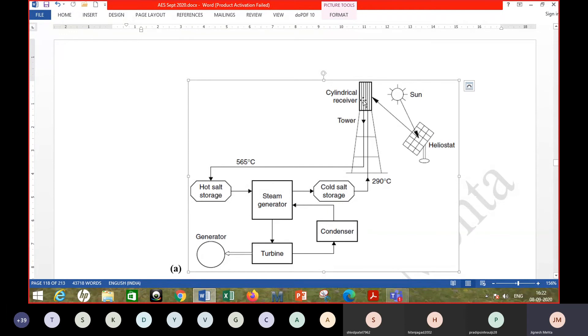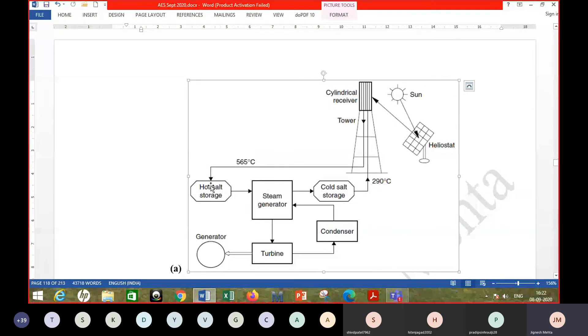In this scheme, molten salt is pumped in at around 290 degrees Celsius and heated to 565 degrees Celsius through sensible heating. Storage is used to operate the plant during off-sunshine hours. The hot salt passes through a heat exchanger acting as a boiler, where steam is generated from the heat exchange between molten salt and water. The steam then drives the regular Rankine cycle — turbine, condenser, and generator producing electrical power. Cold salt is stored and pumped back into the receiver.